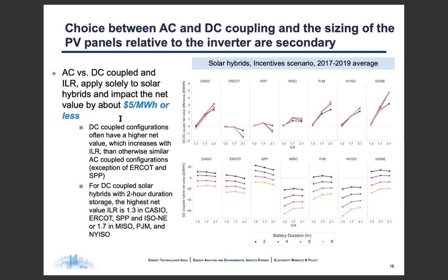Hence, we look in the bottom row exclusively at DC coupled solar hybrids to understand the ILR effects in more detail, concentrating on the 2-hour duration batteries, the darker lines in the lower row. We see that an ILR of 1.3 has the highest net value in CAISO, ERCOT, and SPP, and an ILR of 1.7 in MISO, PJM, and NYISO, and ISO New England also has the highest net value.